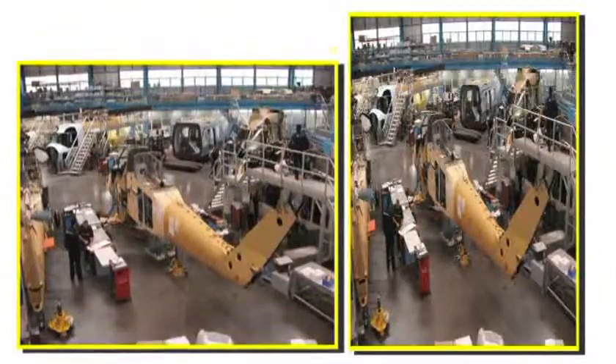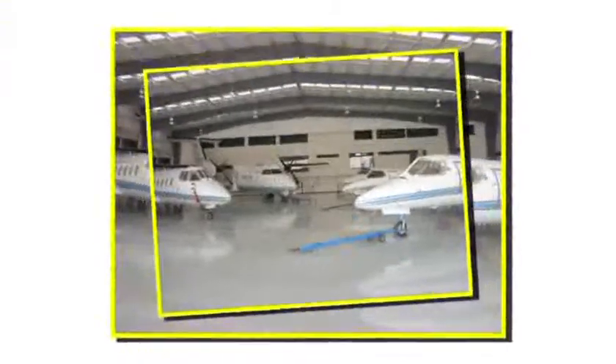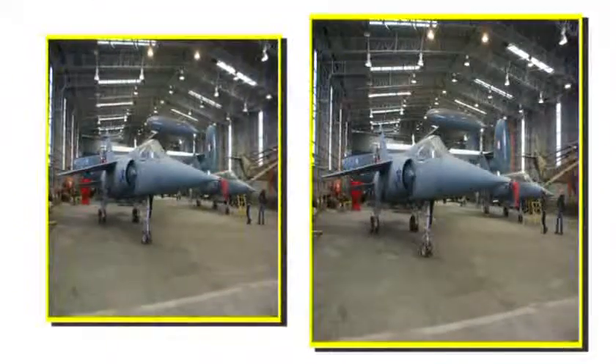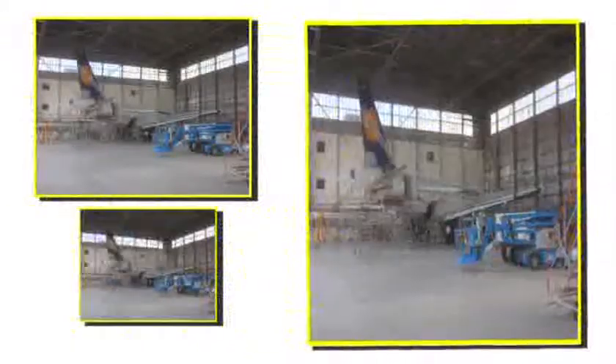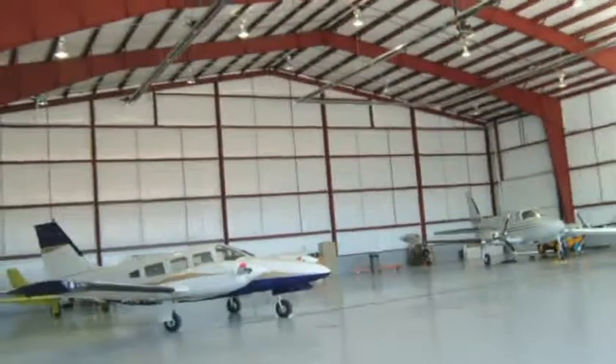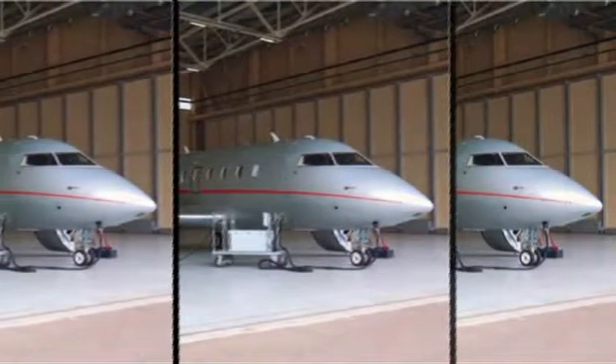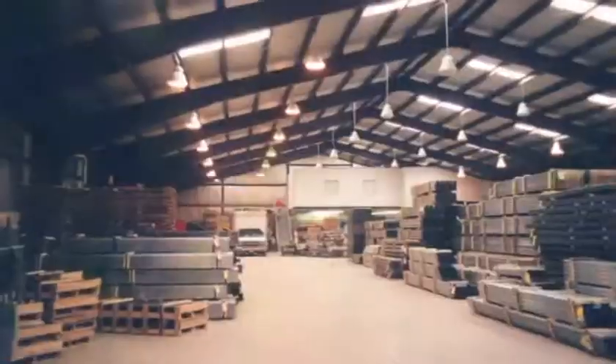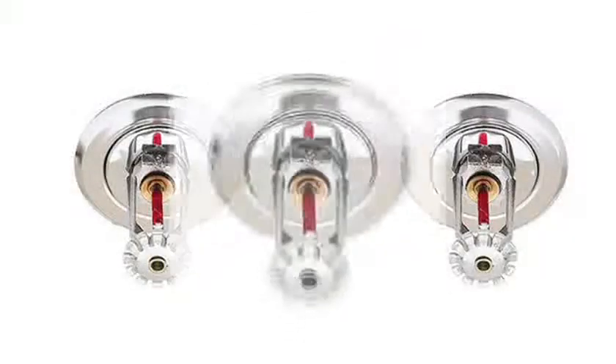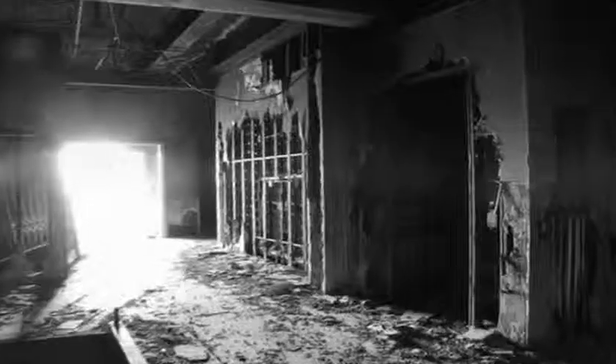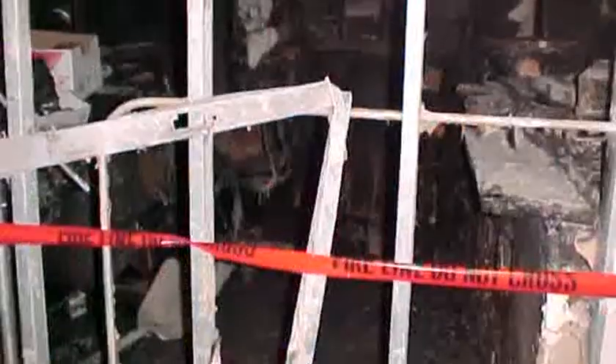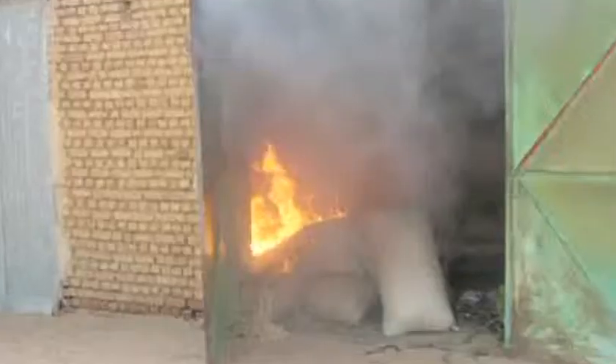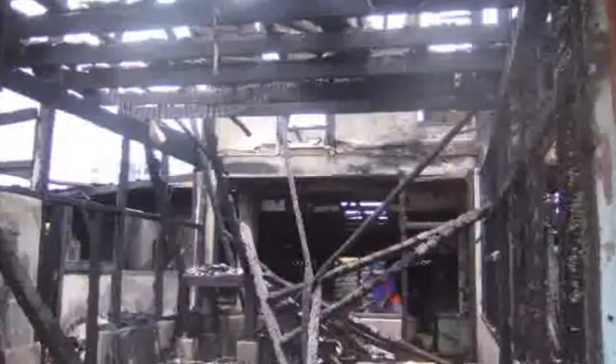Fueled by the extensive presence of petroleum, grease, paint, etc., fires in airplane hangars can potentially end in a devastating explosion. What's more, any damage to the airplane or airplane parts would be very, very, very expensive. And then there are fires in warehouses, where a traditional sprinkler system would cause more damage than the fire itself. What's more, depending on their contents, stored goods can actually fuel the fire.